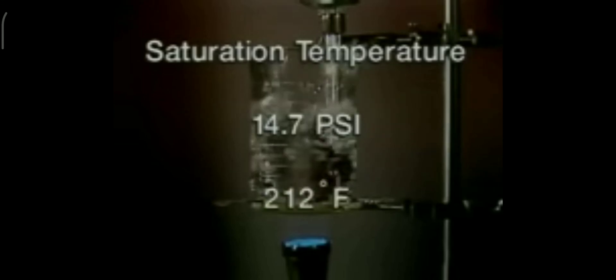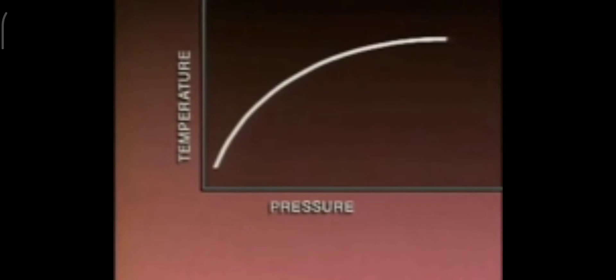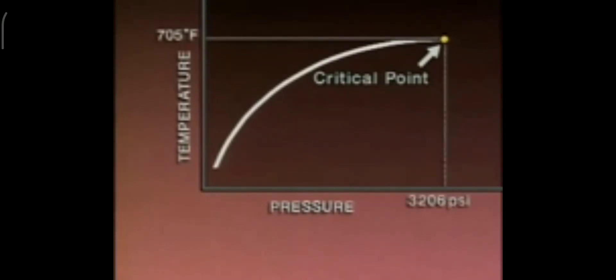At any given pressure, there is a corresponding temperature at which water will boil. This temperature is called the saturation temperature. For example, at standard atmospheric pressure, which is 14.7 PSI, the saturation temperature of water is 212 degrees Fahrenheit. When pressure increases, as it does in this boiler, the saturation temperature also increases. At 1,000 PSI, the saturation temperature of water is 545 degrees Fahrenheit. When the saturation temperatures for water at different pressures are plotted on a temperature versus pressure chart, a line is formed showing the relationship between saturation temperature and pressure. However, this relationship only holds true up to a certain point, called the critical point, which is 705 degrees Fahrenheit and 3,206 PSI.